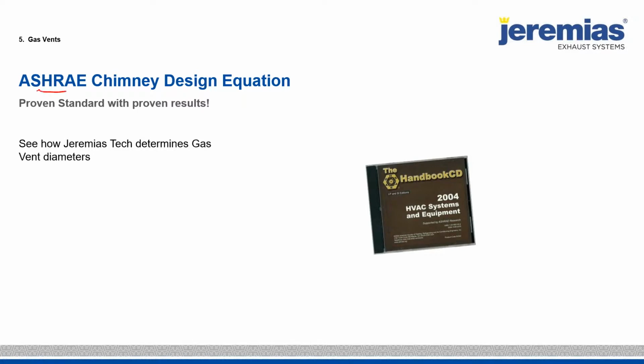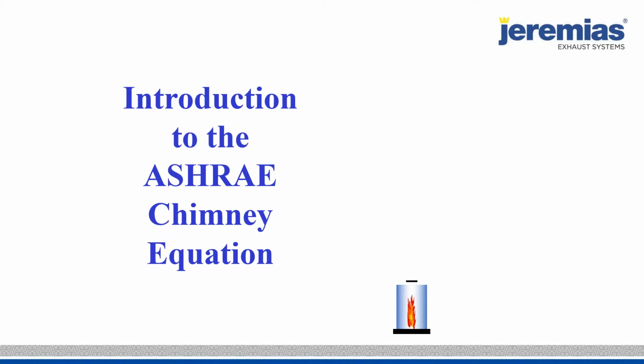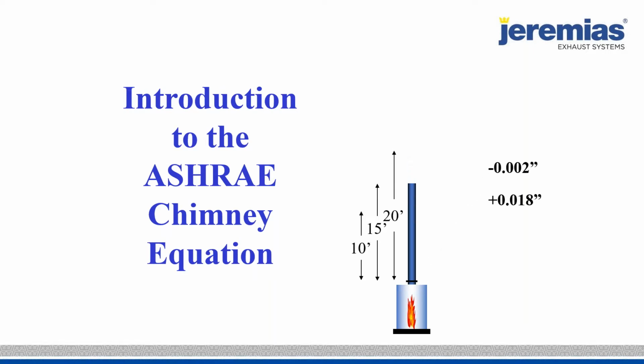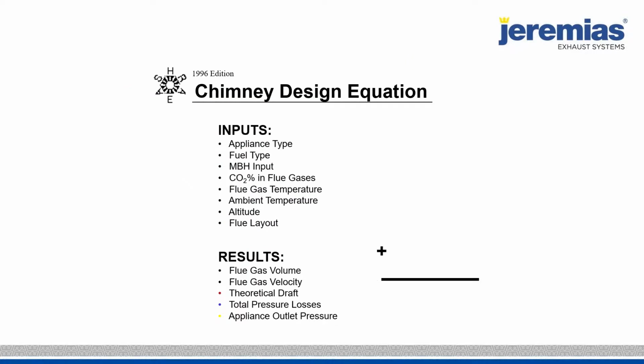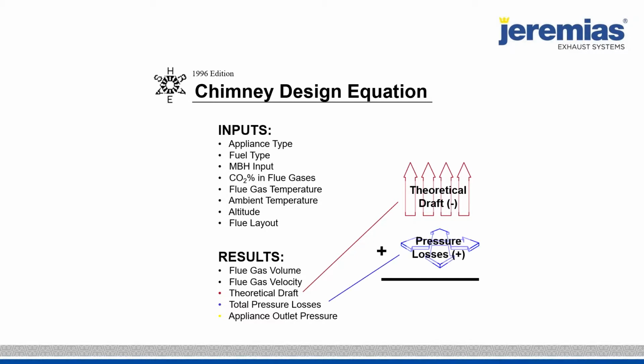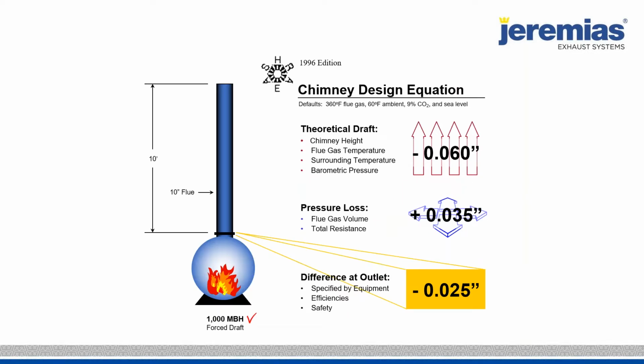So I do want to talk about this chimney design equation. I'm going to go through this very quickly. Please try to follow me, pay attention. We spend hours going through theory in our university systems with the reps, but this equation is a way that we can calculate theoretical draft. We calculate the pressure loss, and then you add these two up together, and that's what you measure at the outlet of the appliance. So we take a look at a 1 million BTU heater, a 10-foot tall stack, a 10-inch diameter flue, and we can calculate a 0.06 inch amount of theoretical draft. We can calculate of all the flue gas volume going through that conduit, a 0.035 inch water column of pressure.